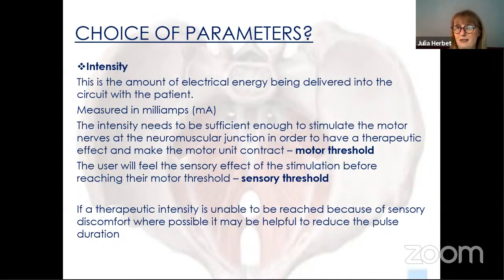And if you can't get a therapeutic intensity up and you're there with the patient and you have a customizable program on your machine, you can reduce the pulse duration, take it down to maybe 125 microseconds, to actually allow that intensity to be tolerated by the patient, because it'll have less effect on the sensory nerves.